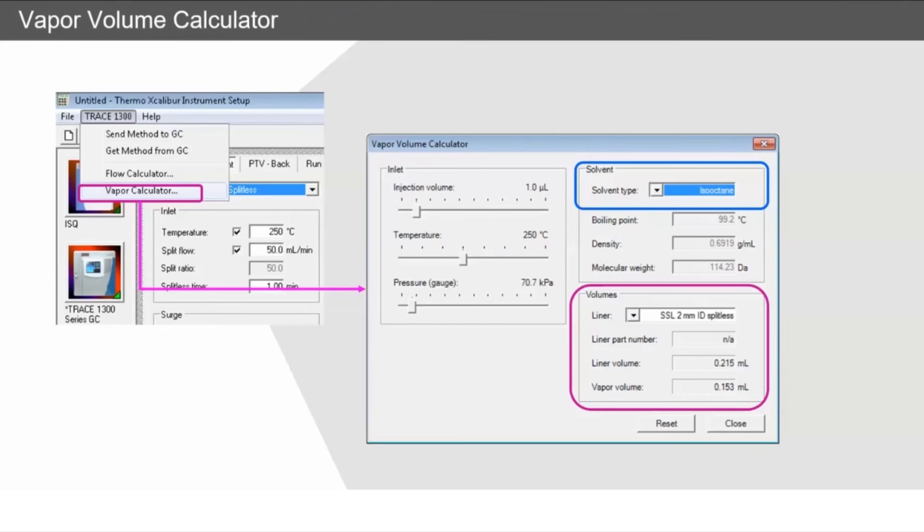We can also see what the liner volume is, and this is really important because we don't want the vapor volume to ever exceed the liner volume - this will cause issues like backflush into lines and carryover. In this example, we've got 0.15 mL vapor volume and a flow rate of 1 mL/min, which means everything's going to come through in less than half a minute. So our splitless time we would set for half a minute. Obviously, other solvents expand more and we need to take this into account.